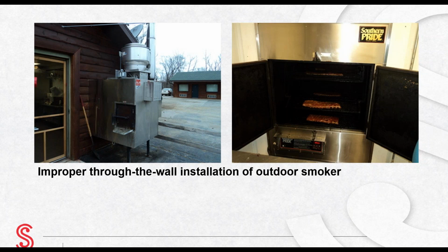This is a through-the-wall installation of a natural gas meat smoking oven with wood log smoke generator for flavoring. This appliance is designed to be used outdoors. While the oven is outdoors, the oven doors open inside the restaurant kitchen. The meat is loaded and unloaded from the oven in the kitchen, and the logs are loaded in the smoke generator outside. The problem with this installation is the wood wall that the oven passes through.